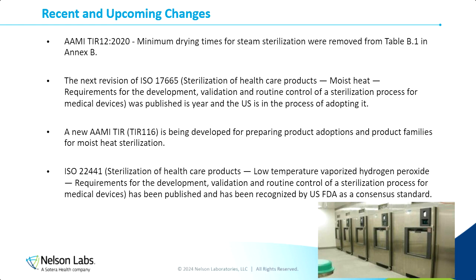validations. And then lastly, ISO 22441 was a document that has been published and has been recognized by the US as a consensus standard. And it is a document that provides information on low temperature vaporized hydrogen peroxide, or VHP, sterilization. So if your device cannot withstand the parameters of a steam sterilizer, then you may want to look into this document and explore the use of vaporized hydrogen peroxide sterilization.